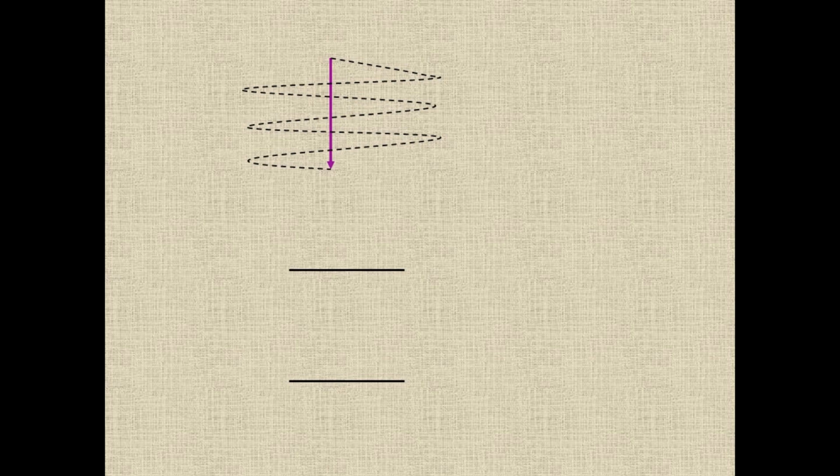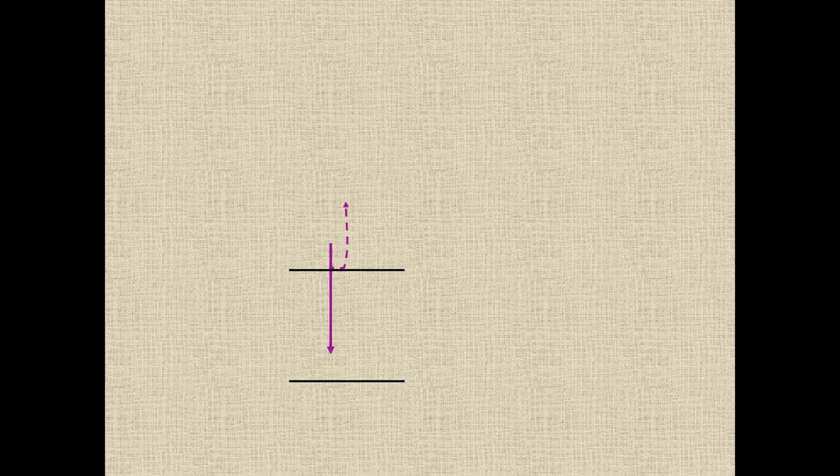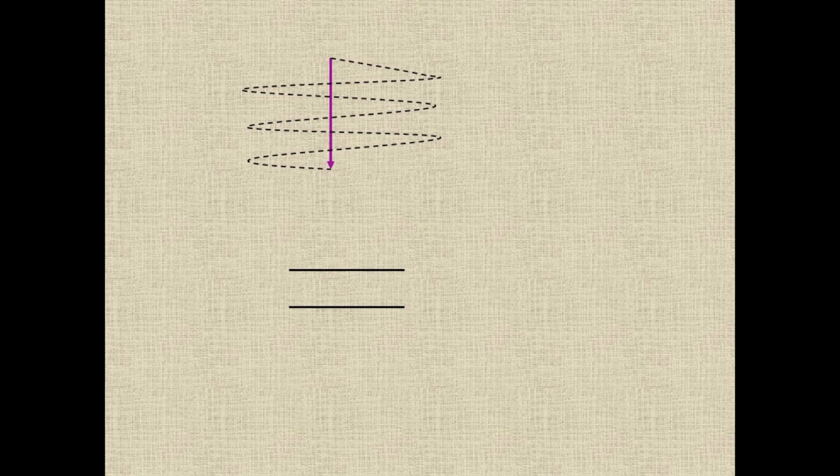As they approach the first reflector, some of the sound energy is reflected back, while the rest of the energy continues on to the second reflector. This is likewise reflected back, and what we have is 2 returning echoes separated by a gap, which means the ultrasound machine can resolve these as 2 different structures. If we put these 2 reflectors closer together, a different effect happens.